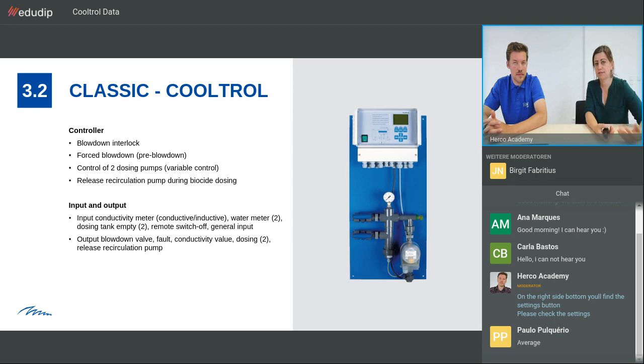As output, we have, of course, the signal for the blowdown valve, the conductivity value, which can be sent to the central system of the client, and the two signals for dosing, on, off, and the release of the recirculation pump. This is necessary because normally the recirculation pump is controlled by the general cooling tower control of the client. But if we want to dose biocide, we need to have the recirculation pump on because the dosing is done on the recirculation pump pressure side. So obviously, then we have to give a signal to the recirculation pump to start operating.